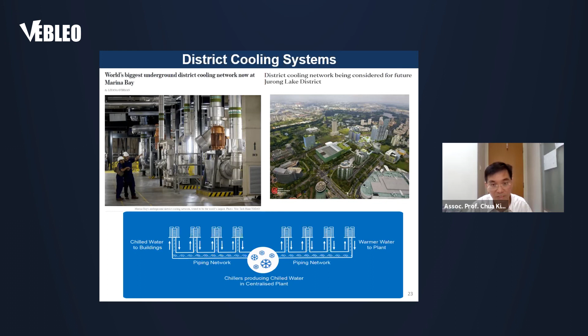Residential buildings and areas where the users are just basic residents of the apartment, right? So the impact of this is that if we can distribute the water, previously at 5 to 6 degrees, to all the clusters of buildings through the district cooling system, instead of 5 to 6 degrees previously, because we do not have the luxury of the dehumidification technology like the membrane or the super absorbent, now we can do that at a different temperature, right?